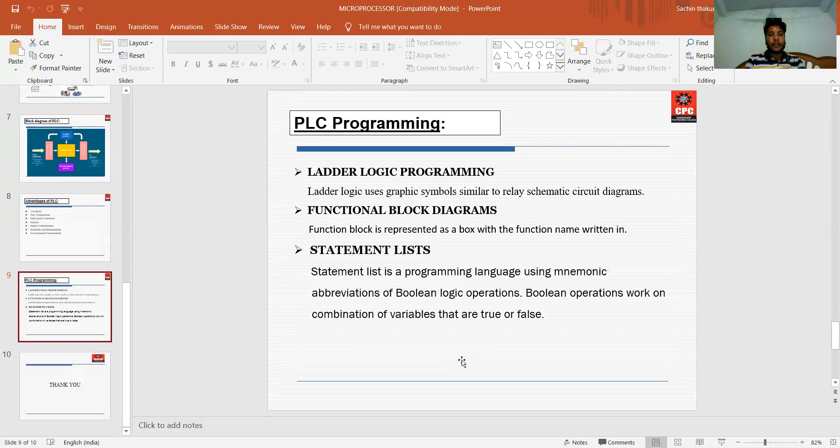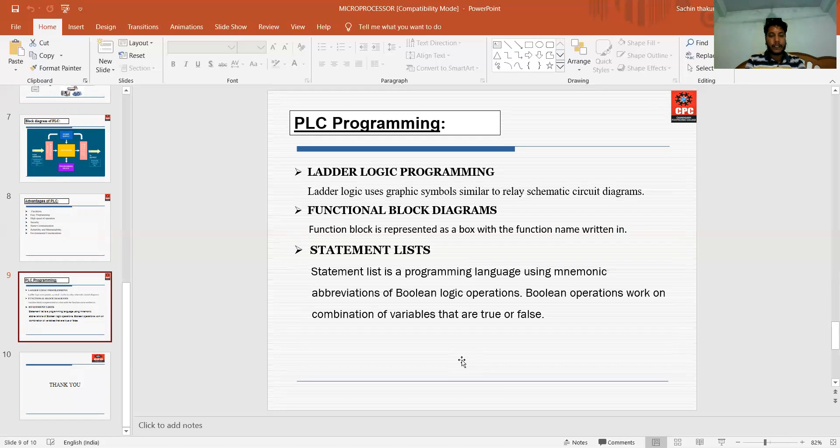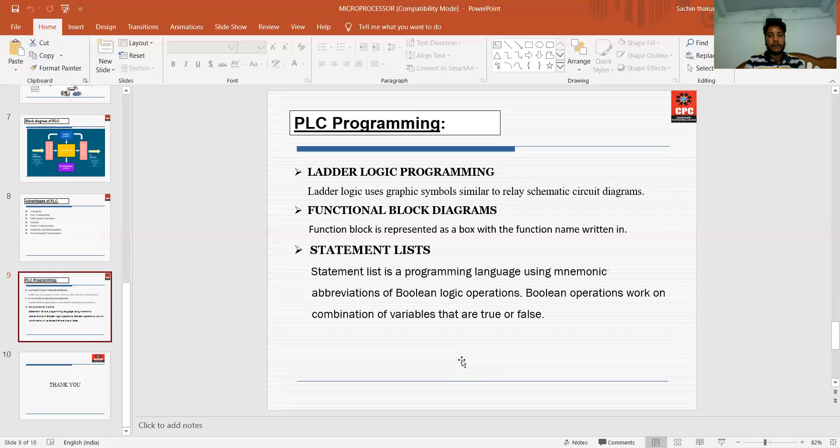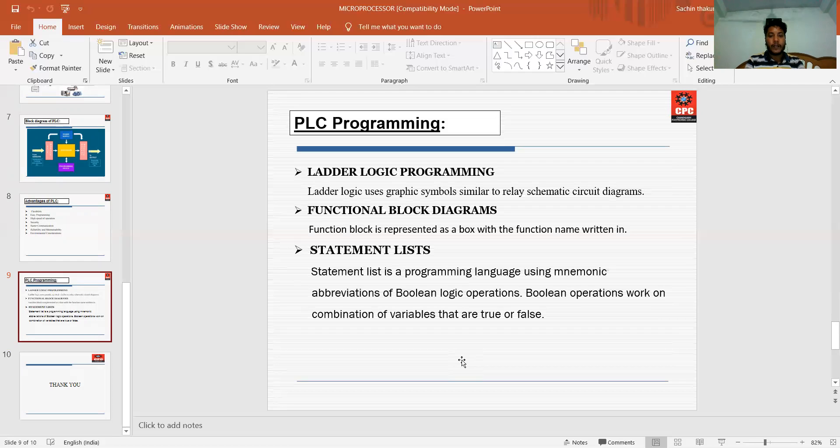Next is PLC programming. There are three main programming types for PLC. First is ladder logic programming, second is functional block diagrams, and third is statement list. In ladder logic programming, we use logical graphic symbols similar to schematic circuit diagrams - for example, NOR gate, NAND gate, etc. In functional block diagrams, it is represented as a box with function name written. In statement list, it is a programming language using mnemonic abbreviations of Boolean logical operations. Boolean operations work on the combination of variables that are true or false.